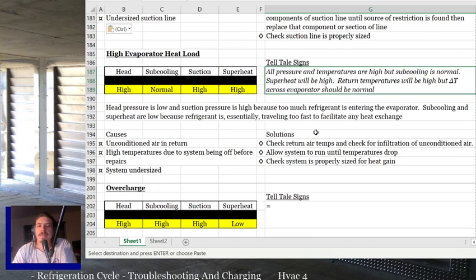High evaporator heat load. So basically, it's hot as hell inside, and you got to cool it down. So high evaporator heat load should be pretty easy. High head pressure, normal subcooling, high suction pressure, high superheat. So everything's high, but your subcooling should be normal. Now on a fixed orifice, what's normal, right? There's no charts that tell you what your subcooling should be on a fixed orifice system. But basically, everything's just high, but it doesn't look like an overcharge because you don't have low superheat. It doesn't look like a dirty condenser. It doesn't look like a non-condensables in the system issue, anything like that. Then it's probably just a high evaporator heat load.